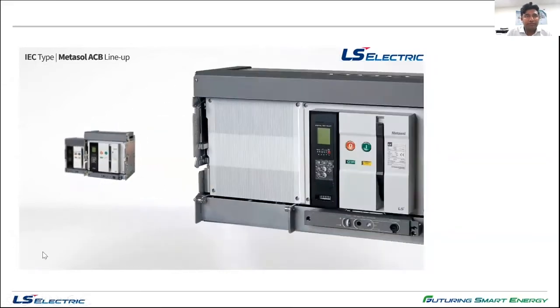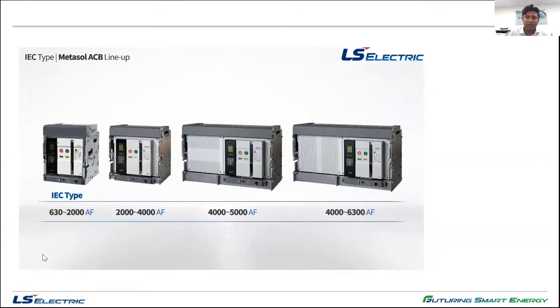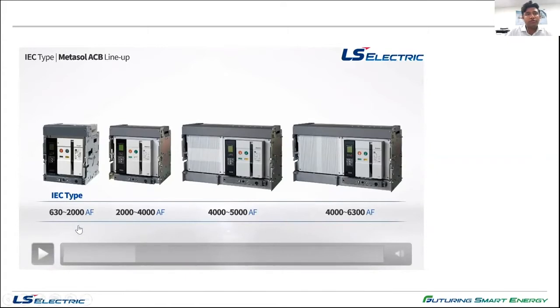Now coming to the Metasol series, here we have 4 different frame sizes, unlike the Susol. Susol has 3 frame sizes, and those 3 frame sizes are available in Metasol also. In Metasol we have one additional frame size, which is the 4000 to 5000 amps frame size. The initial frame size is represented here as up to 2000 amp frame size. In this Middle East condition, we normally use up to 1600 amps in the first frame size. This is because of the temperature rise of 50 degrees to be met here, as well as the horizontal and vertical segment usage. If you choose 2000 amps in the first frame size, horizontally it is difficult to get 50 degrees. So we recommend using up to 1600 amps in the first frame size.